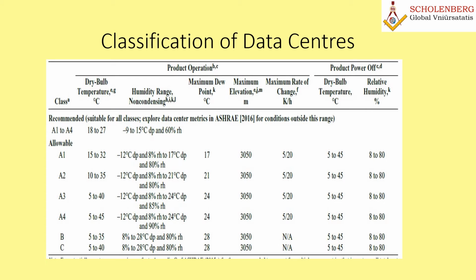Then what is this dew point? What is this minus 9 degrees to 15 degrees? What is this all about? Why is the dew point coming into the picture? Well, as per the latest study conducted by ASHRAE, it has been clearly evident that no significant proof has been found that relative humidity has a direct impact on static electricity and may affect the machines. There is no direct relation found between these two. So here 8% RH is also allowed, up to 80% RH at the maximum. That has relieved the life of the designers to a great extent.